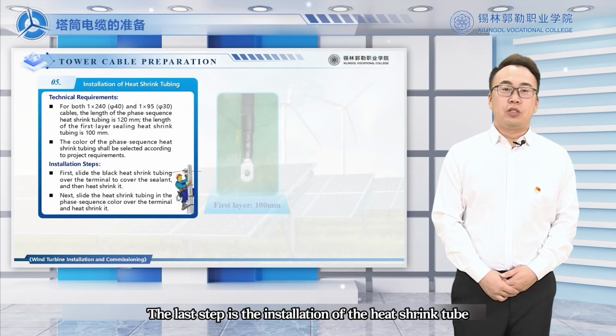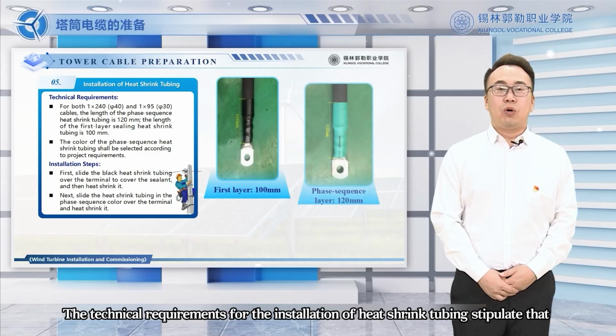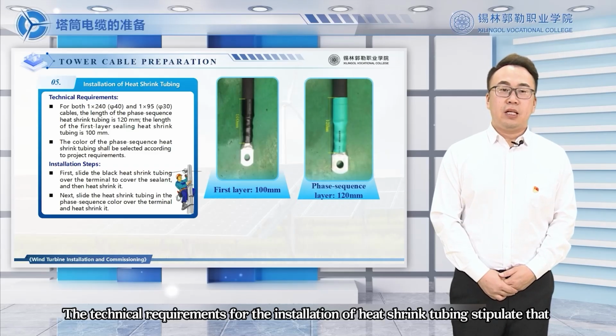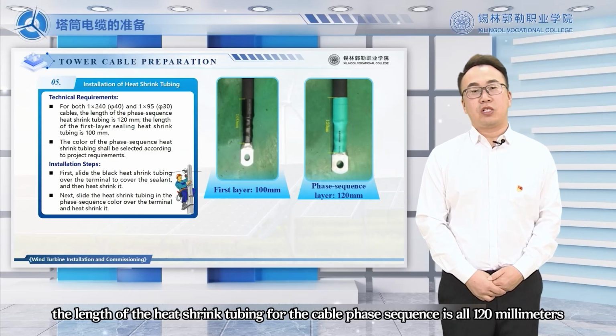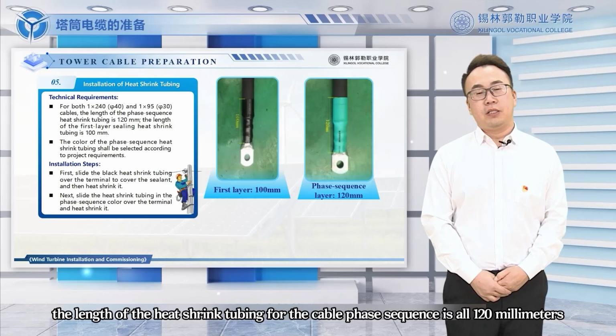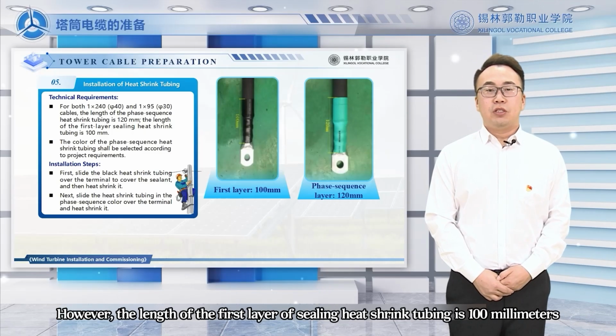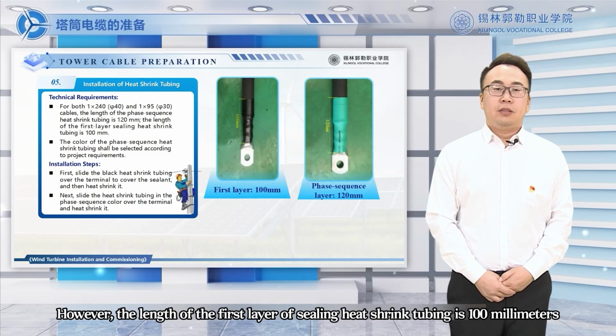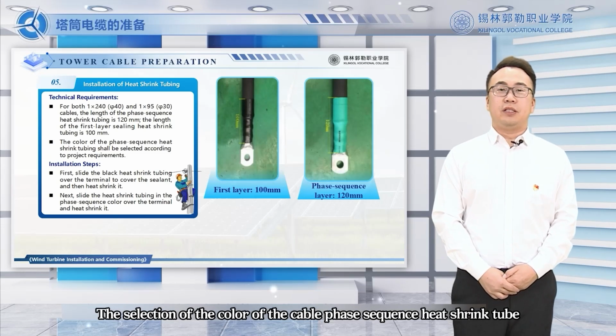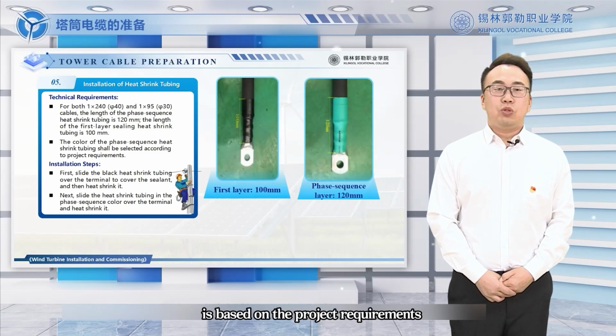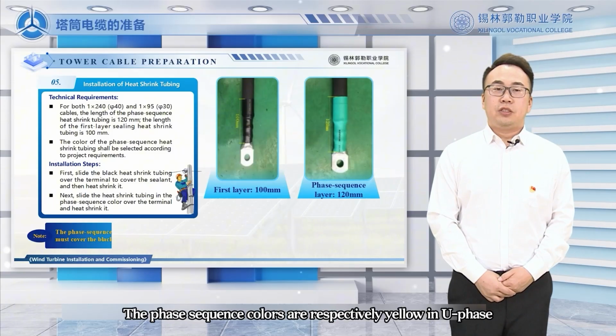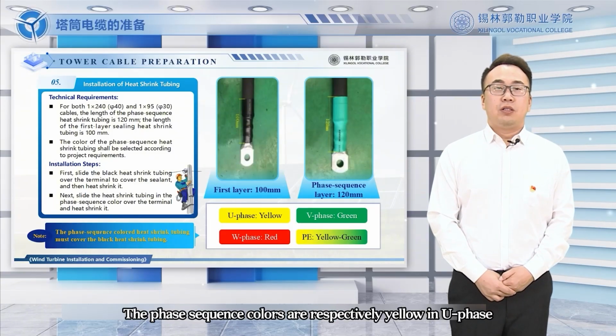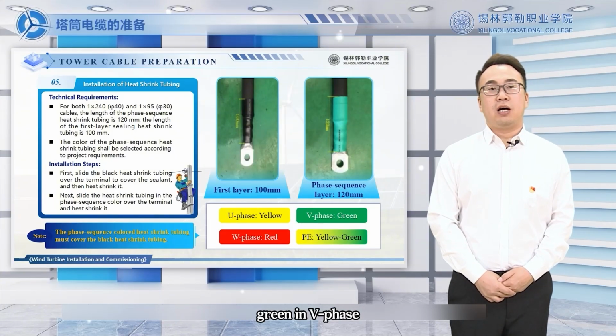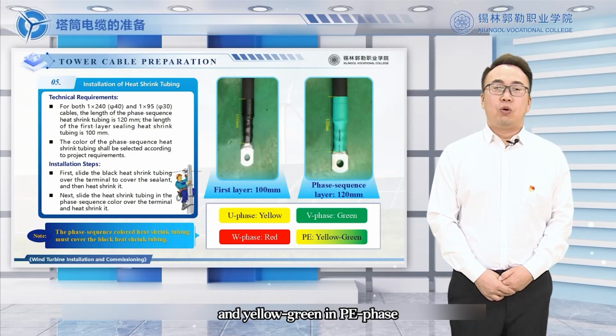The last step is the installation of the heat shrink tube. The technical requirements stipulate that the length of the heat shrink tubing for the cable phase sequence is all 120 millimeters, while the length of the first layer of sealing heat shrink tubing is 100 millimeters. The selection of the color of the cable phase sequence heat shrink tube is based on project requirements: yellow for U phase, green for V phase, red for W phase, and yellow-green for PE phase.